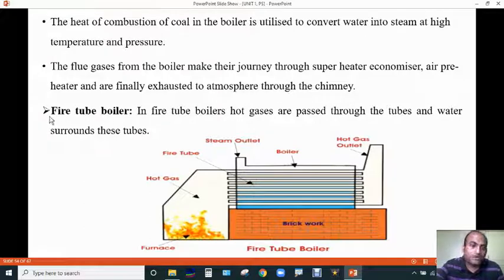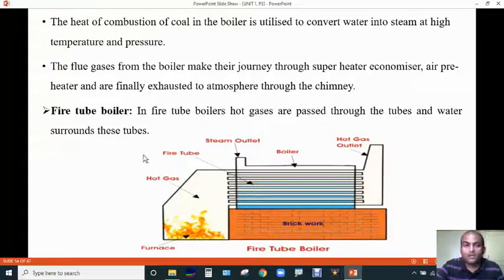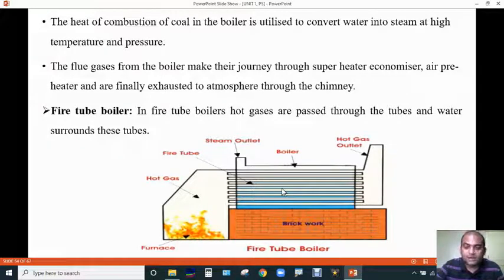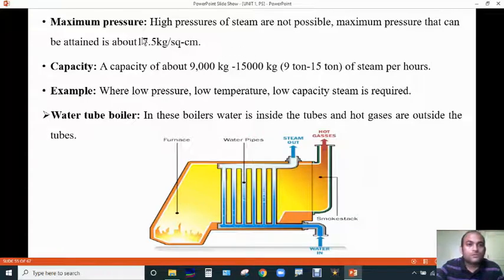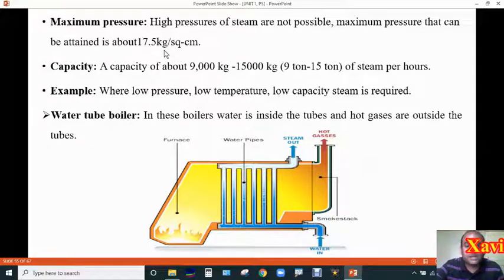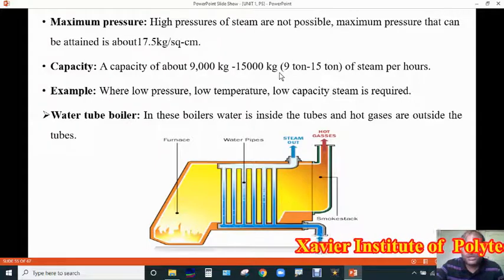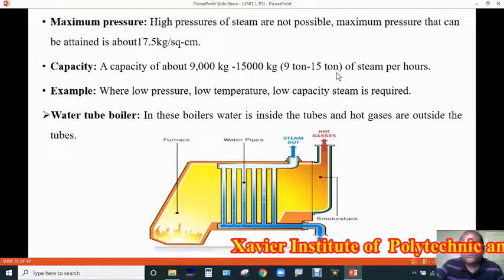There are two types of boilers. The first one is the fire tube boiler. In fire tube boilers, hot gases are passed through the tubes and water surrounds these tubes. Here the furnace is at one end, the hot gases enter the tubes and exit at the hot gas outlet. The maximum steam pressure is about 17.5 kg per square centimeter, and the capacity of steam generation is about 9,000 kg to 15,000 kg, which is approximately 9 to 15 tons of steam.